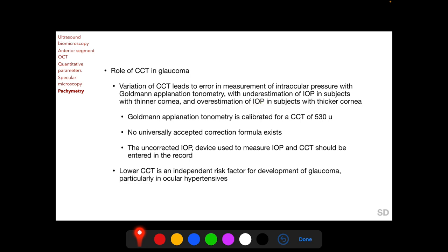A thinner cornea leads to underestimation of IOP recorded with the Goldmann applanation tonometer, and a thicker cornea leads to overestimation. The Goldmann applanation tonometer is calibrated for a CCT of 530 microns, meaning that at 530 microns the IOP recording is accurate — close to the normal average CCT of 536 microns. No universally accepted correction formula exists for IOP error due to CCT variation. When recording IOP, we should ideally note the uncorrected IOP, the device used, and the CCT.